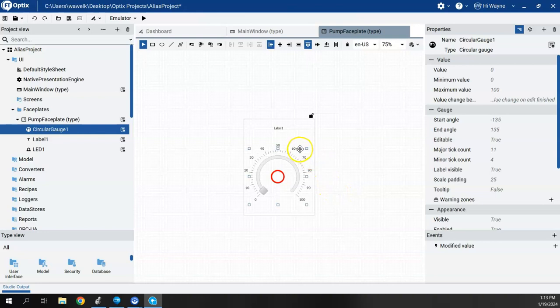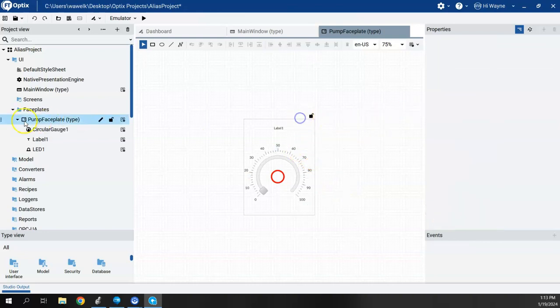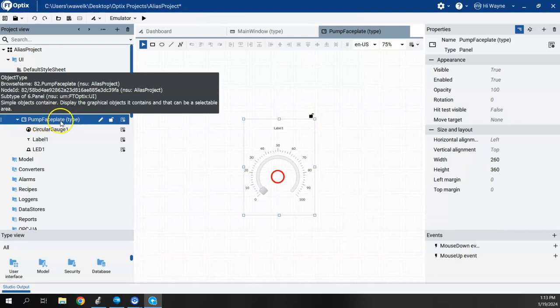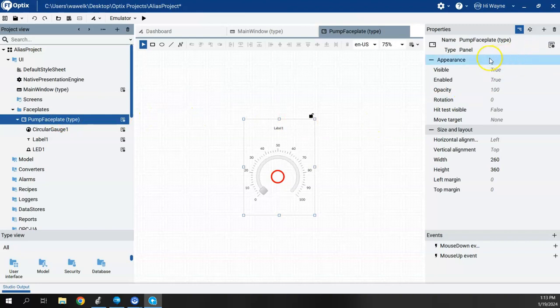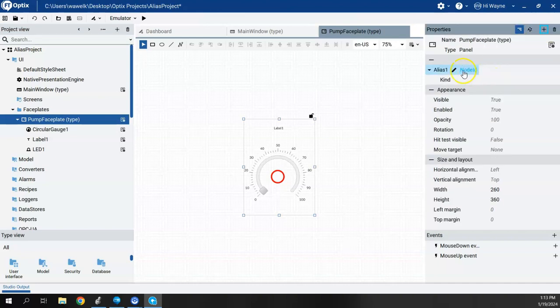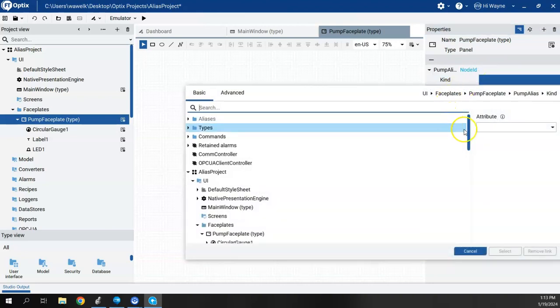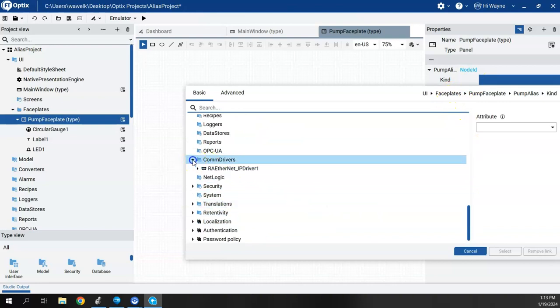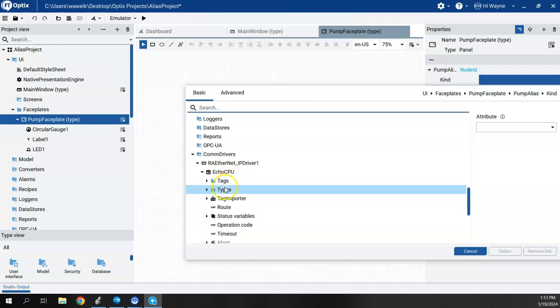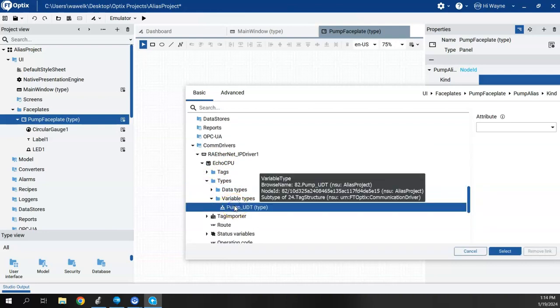Now I'll click on the Pump Faceplate itself at the top level and hit the plus symbol to access its properties. I'll say New Alias — it creates an alias called Alias One. I'll rename this to Pump Alias. For the Node ID I'll leave it alone, and for Kind I'll assign it to Com Drivers > Echo CPU > Types > Variable Types > Pump UDT Type.